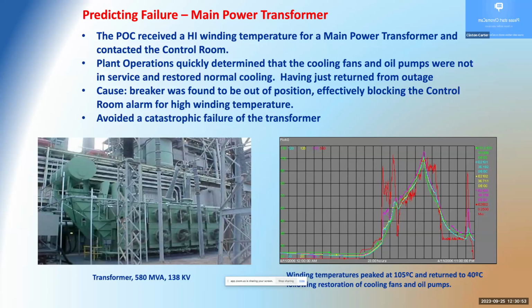And when you see all these fans on the side of the transformer here on the left, so they went out there, and what they saw was all of the cooling for this transformer was off. Their lube oil pump or the oil pumps and these fans that keep the electrical windings cool as hundreds of megawatts are flowing through this thing onto the grid. All that cooling was off. This transformer was in an ultimate failure mode, and when it failed, it would have been a massive event, and that plant would have been shut down permanently, and a huge fire would have resulted. It would have caused probably a lot of damage, definitely a lot of damage. So we avoided a catastrophic failure.